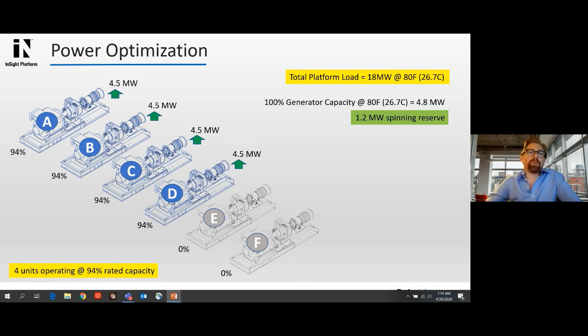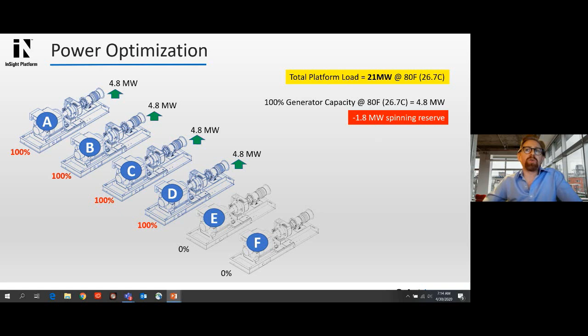Now, if we were to look at a load increase on this particular platform from 18 megawatts up to 21 megawatts, again with the ambient temperature the same at 80 degrees Fahrenheit or 26 degrees Celsius, we would notice that even if the engines went up to their max rated capacity of 4.8 megawatts, we would have a 1.8 megawatt spinning reserve deficit. In the absence of any mitigations, these 4 running machines would attempt to assume the load and try to continue to produce power. But inevitably, they would not be able to reach the demand, and then they would start tripping offline and the platform would go dark. So for power optimization, we have a few different options to explore.